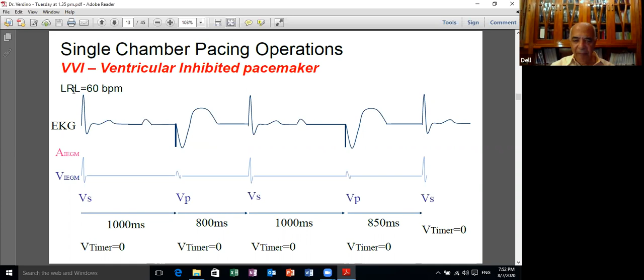This is in contrast to the situation with the DDD pacemaker, which has a tracking function, and it tracks the atrial activity, and it doesn't have one clock like the VVI pacemaker. It has 2 clocks. It has a clock which indicates the AV clock, which corresponds to the PR interval, and it has another clock which is a VA clock, or the atrial escape interval, which is the interval that elapses from the sensed or paced ventricular activity to the next atrial paced activity.